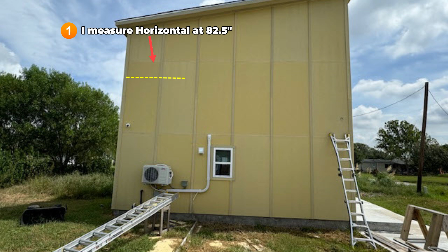Step 2. Drill the access hole. Drill a hole into the wall where the insulated and pre-flared line set, communication wire and condensation drain line will pass through. Use a drill bit that creates a 3-inch diameter hole, and then cover it with a PVC line kit to protect, organize, and insulate the refrigerant lines and electrical wiring, ensuring durability, efficiency, and a cleaner installation.